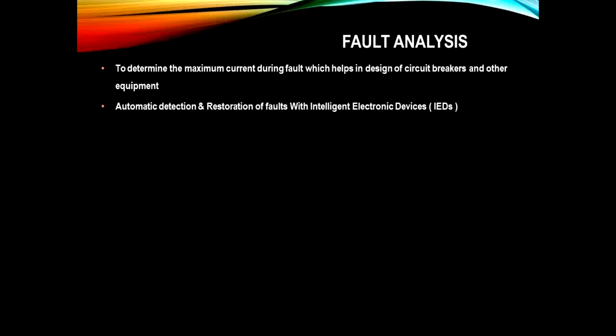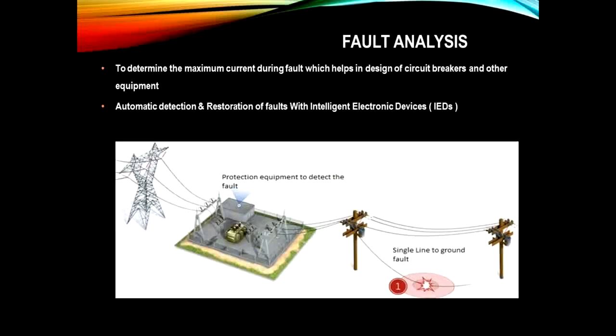Next is automatic detection and restoration of faults with intelligent electronic devices. For example, take a transmission line somewhere away from the generating station. Assume one line fell down due to a tree falling on it or some natural disorder. How do you find out where the fault occurred? For that, we use a distance relay. So there are different protecting devices or components which can be used for this purpose.